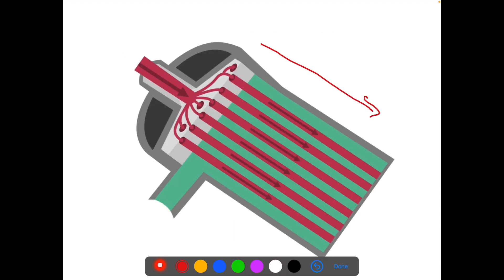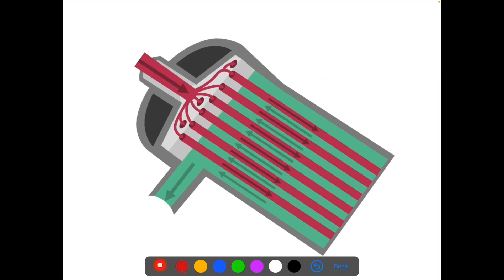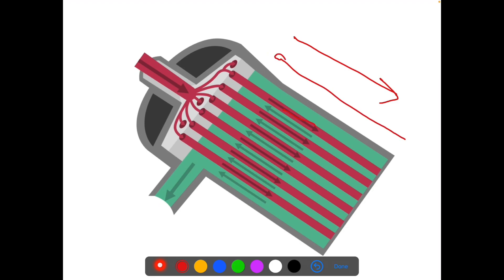The blood flows in one direction, and for the exchange to take place — the purification of the blood — the dialysate needs to flow in the opposite direction. So blood flows in this direction and dialysate flows in the opposite direction. This is called the counter-current mechanism.